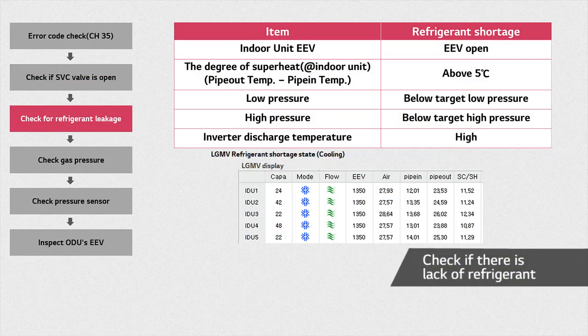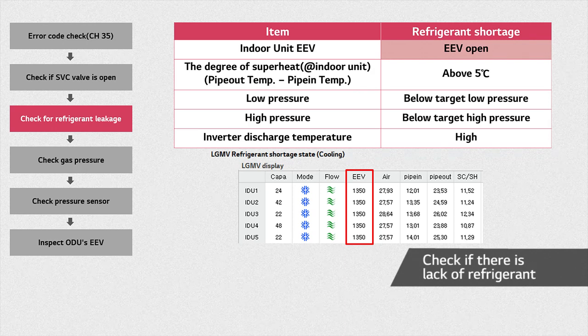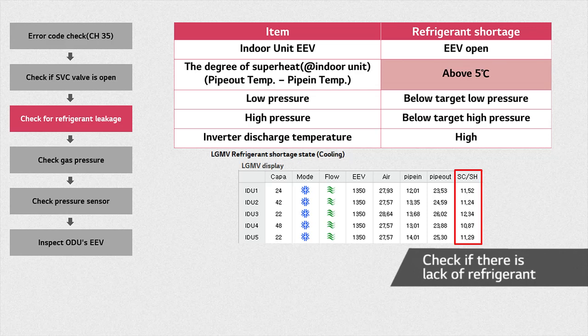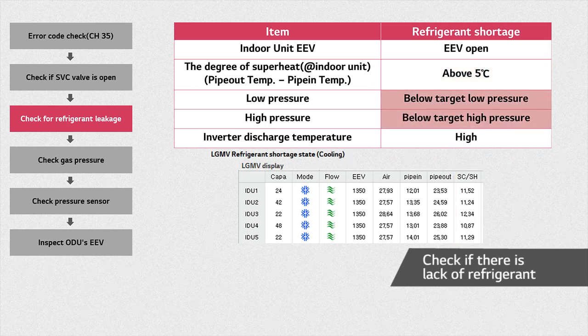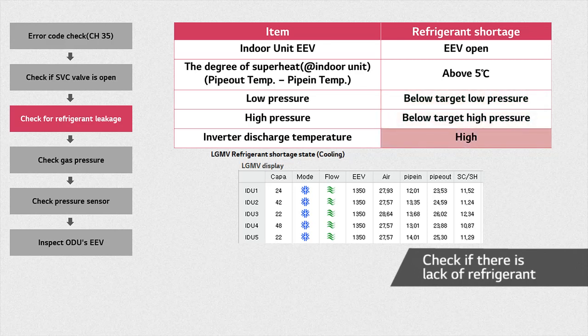Start by checking if the refrigerant is insufficient using LGMV. Through LGMV, you can also check the cycle. You can tell that the refrigerant amount is lacking when the indoor unit EEV is fully open and the degree of superheat at the indoor unit is above 5 degrees. Superheat is the difference between the pipe-out temperature and the pipe-in temperature of the indoor unit. Also, when both low and high pressure are below the target pressure for each, or the discharge temperature of the inverter is higher than usual, you can tell there is a lack of refrigerant.